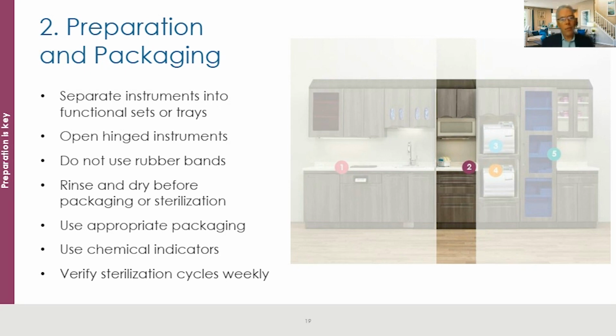Now the second part of the sterilization area is prep and packaging, where we get the instruments ready to go into the autoclave. Again, these instruments are separated into sets or put into cassettes if you're using them, which I highly recommend. I love cassettes. Hinged instruments are opened. Remember, don't use rubber bands, they don't hold up well in heat at all.